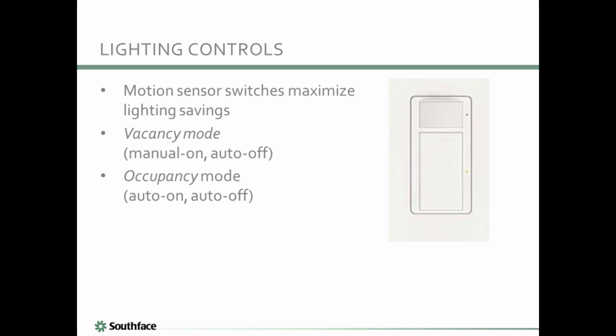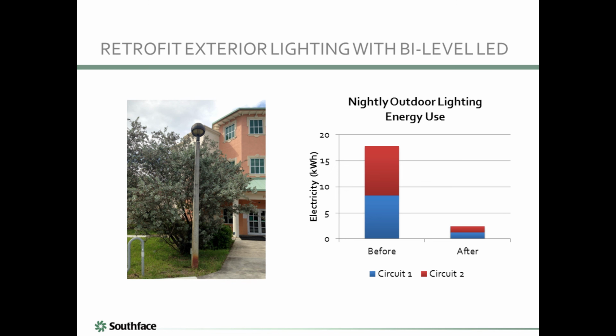Combining lighting retrofits with lighting controls can maximize savings. When installing motion sensor switches, they have two operating modes. The first mode is vacancy mode. This requires a manual on and automatic off. Vacancy mode produces the most savings. It's appropriate for offices and classrooms, especially whenever they're adjacent to a corridor. It basically reduces false triggers so that lights aren't coming on and off whenever the room is not occupied.